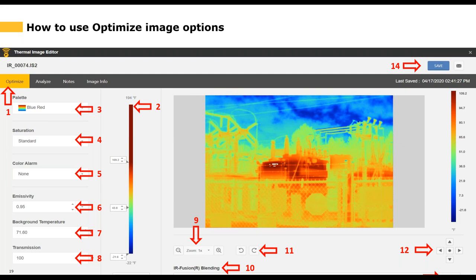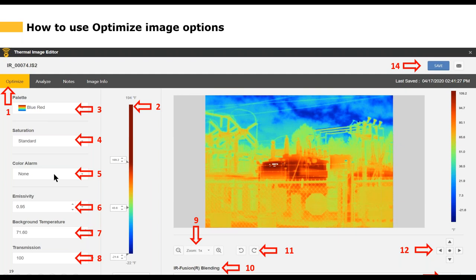Next we have Saturation. You use the saturation option to specify what color you want things to appear that are outside of the span — hotter than the hottest point or colder than the coldest point. For instance, things hotter than the hottest point of 109 appear in a dark burgundy color. You can see a small area of the chart in that dark burgundy, indicating those areas are hotter than the hottest point in our span.